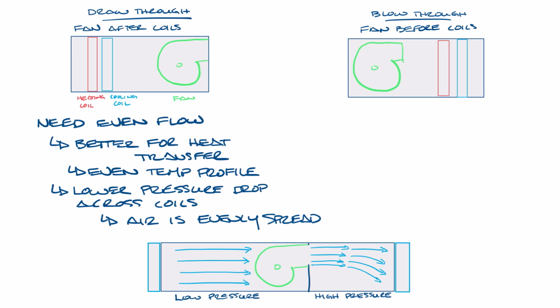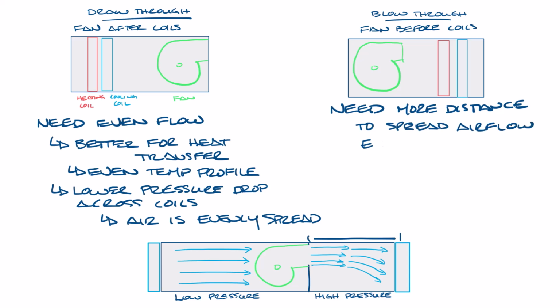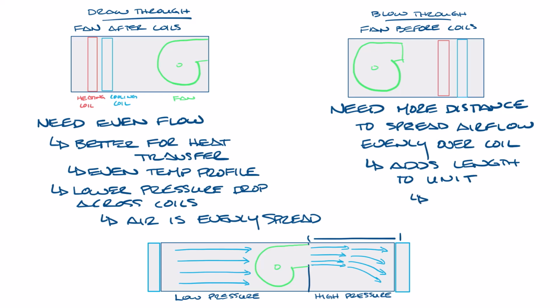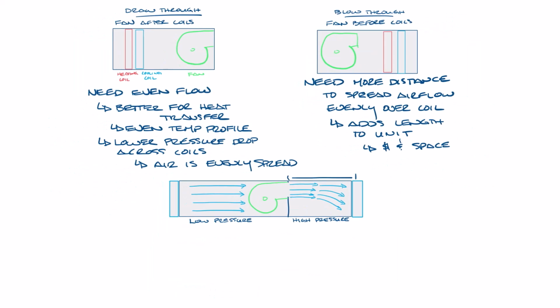Now let's look at what happens if you put the water coil in a blow-through configuration. Since the air is leaving the fan at the top of the ductwork, it needs time to spread out to get good coverage over the water coil, so you may need to put the coil farther away from the fan to allow the airflow to become more uniform. This adds length to the unit, which adds cost and takes up space. Let me make a little bit of room.